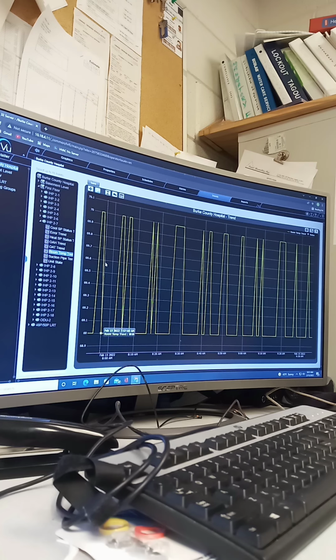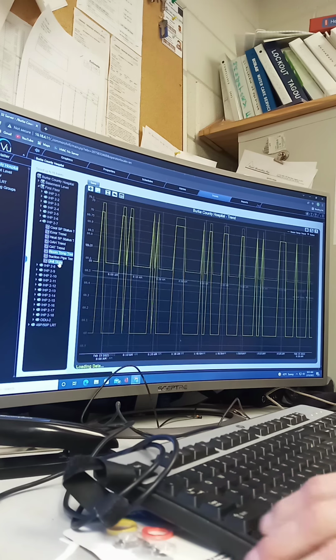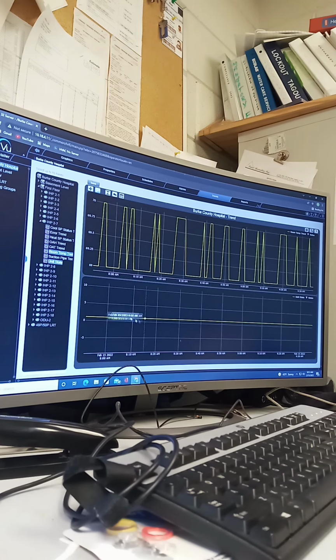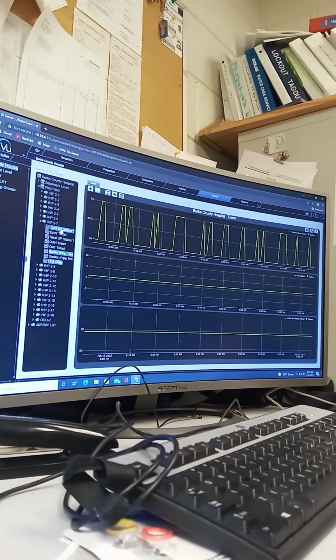But I can see more than one thing. I want to look at the room temperature, but let me see what the unit state was over a period of time. Was it in heating or cooling? If I can go up here, I can look at set points, the cooling status. Set point status was 70, right? And then I can start moving these things in here too to see the actual temperature going above and below those set points. So all sorts of things I can do with trends in here, okay? And that's the nice thing.